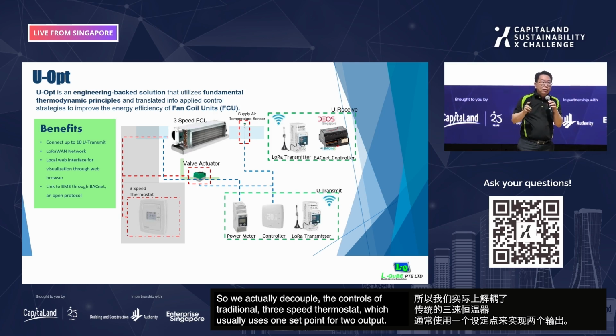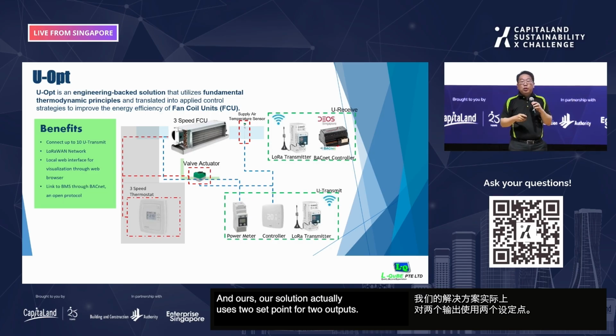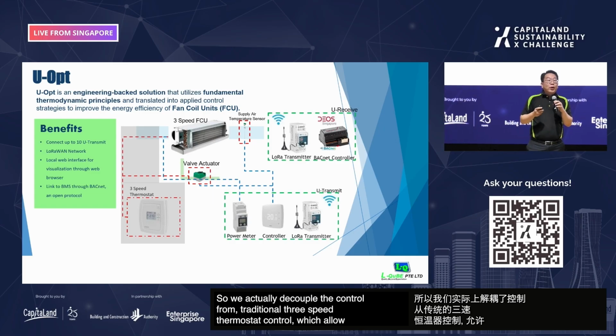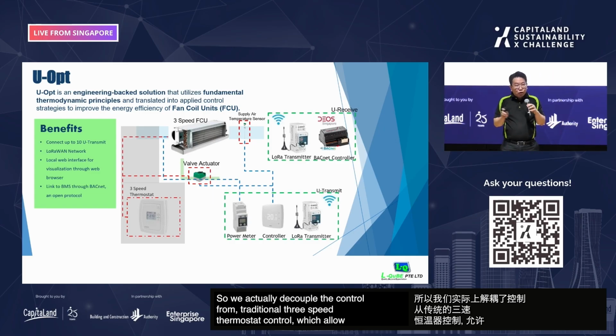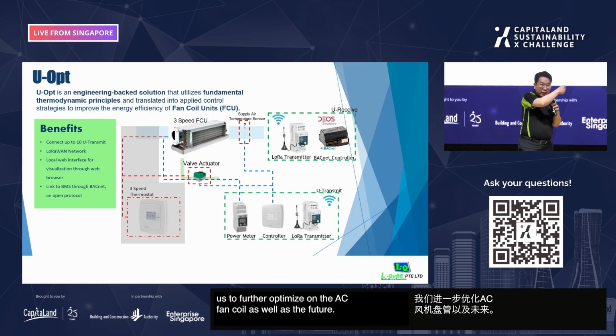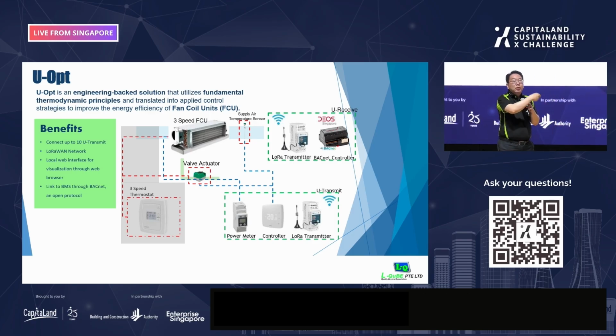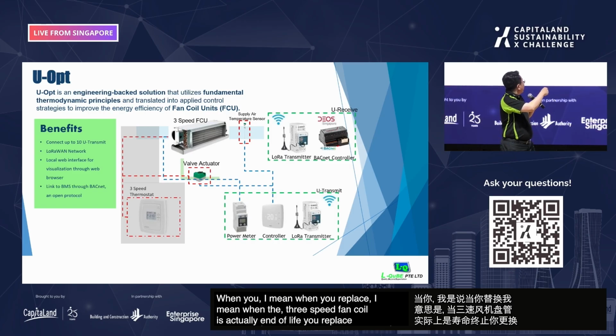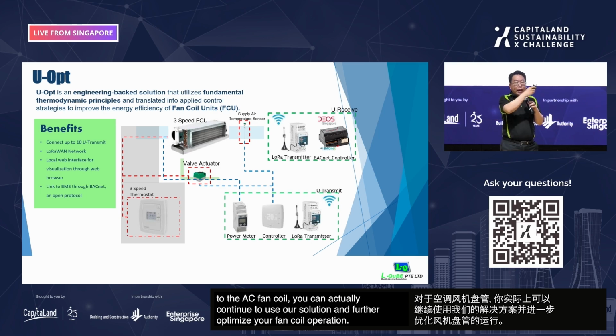So we actually decouple the controls of the traditional 3-speed thermostat, which usually uses 1 set point for 2 outputs, and our solution uses 2 set points for 2 outputs. This decouples the control from traditional 3-speed thermostat control, which allows us to further optimize the AC fan coil, as well as in the future when the 3-speed fan coil is end of life and you replace it with the EC fan coil, you can continue to use our solution and further optimize your EC fan coil operation.